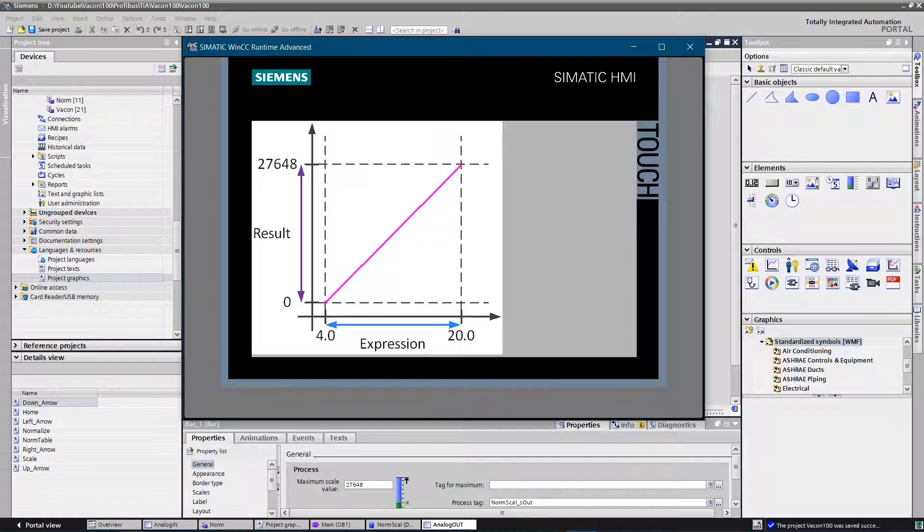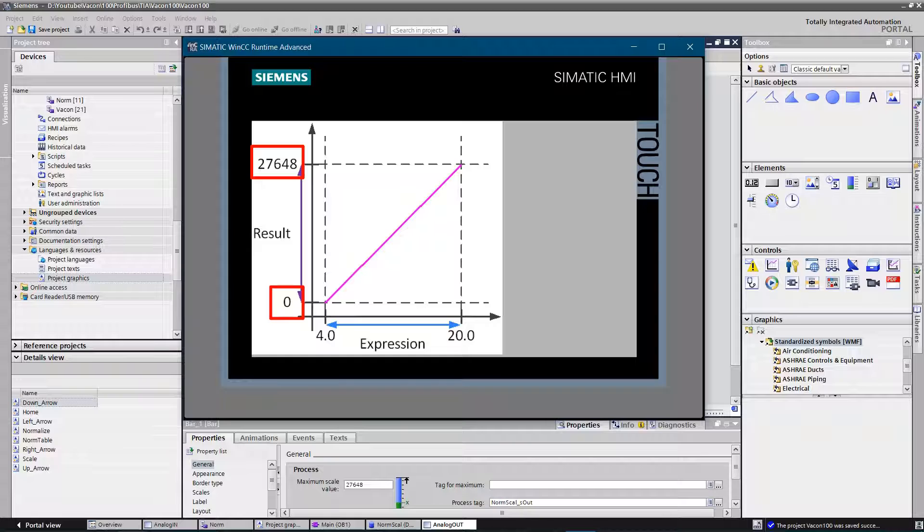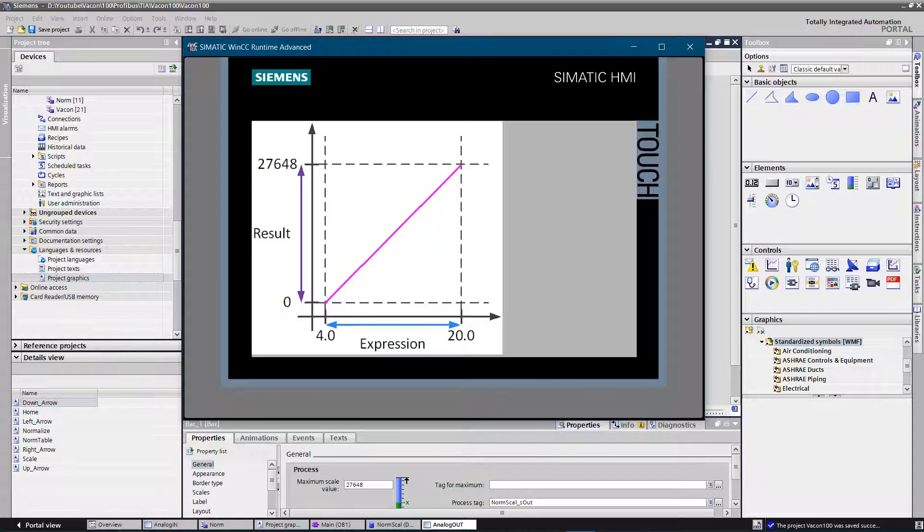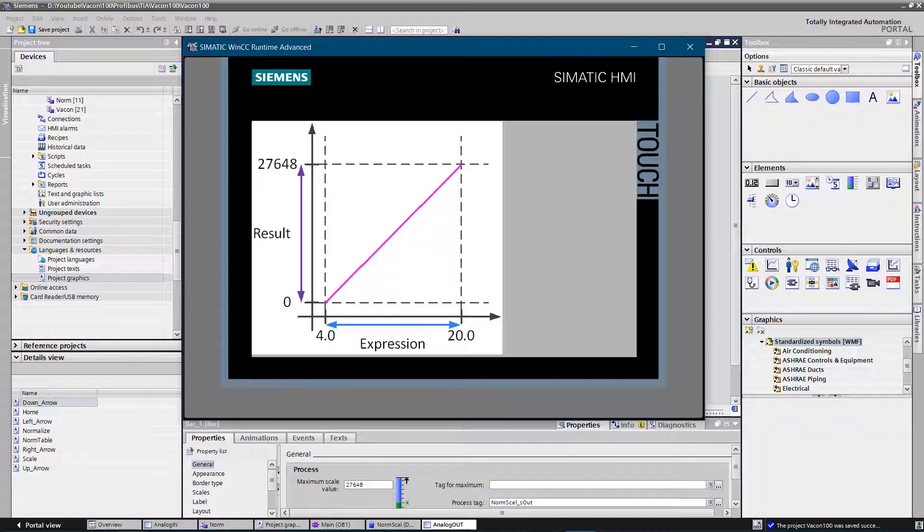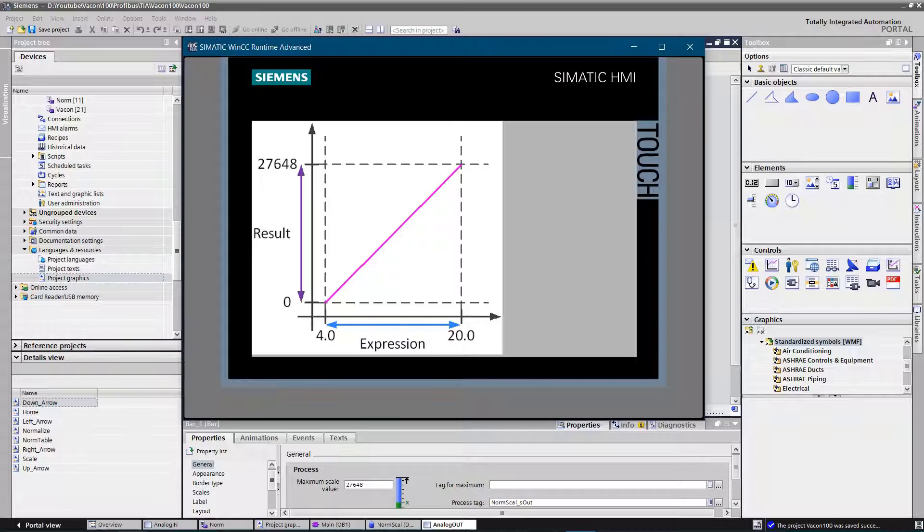In Siemens world, standard value range of analog signal is within 0 and 27,648. So for example, if you have a proportional valve that is controlled by signal 4 to 20 milliamps, then digital to analog converter operates within range of 0 to 27,648 where 27,648 applies to 20 milliamps.